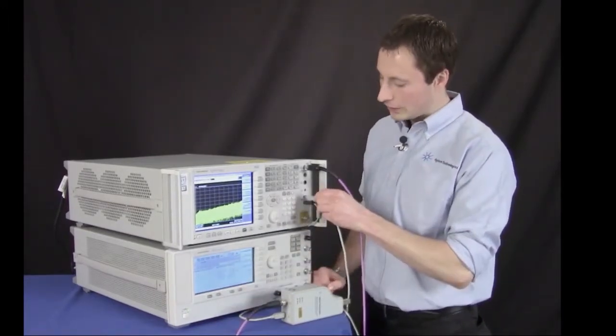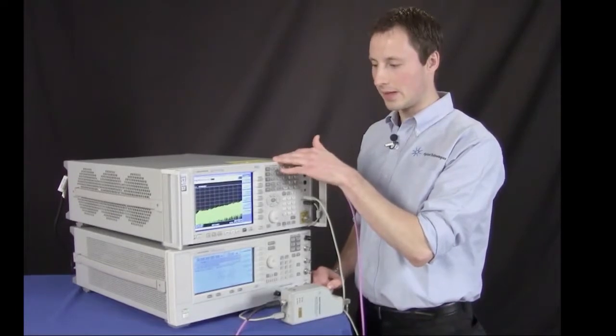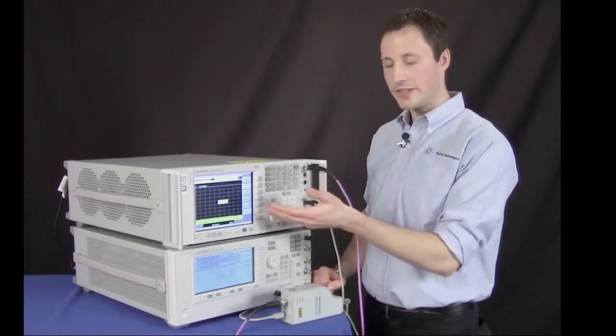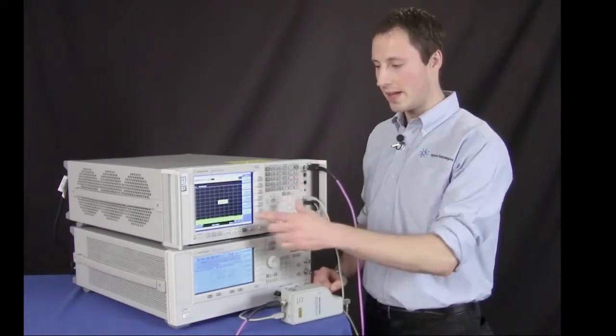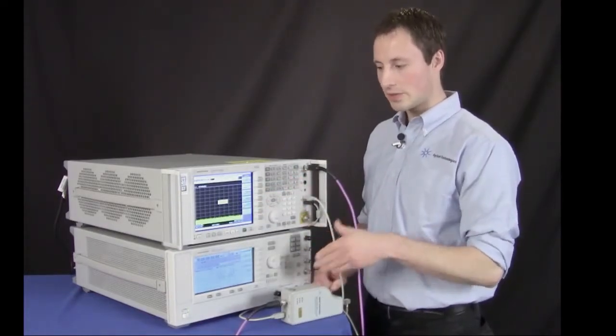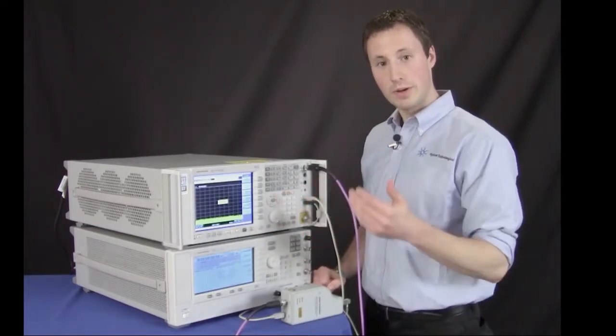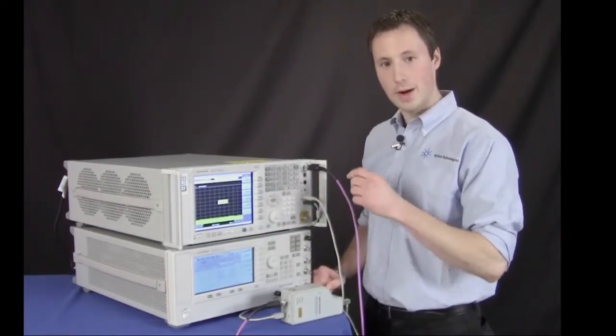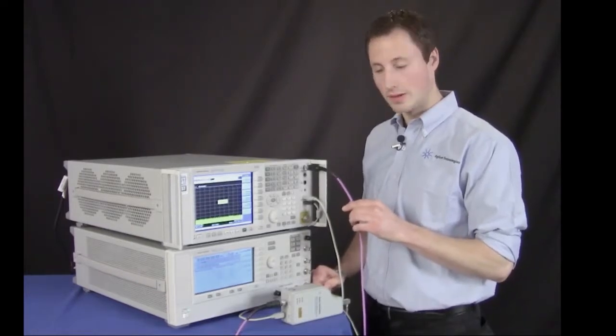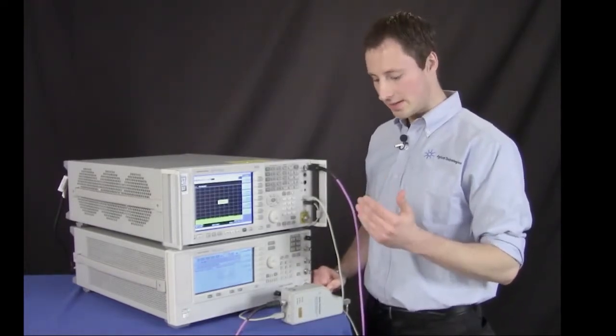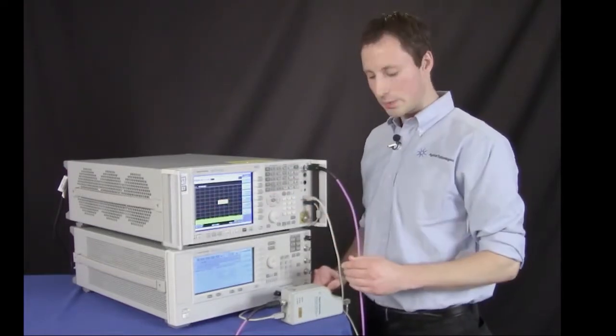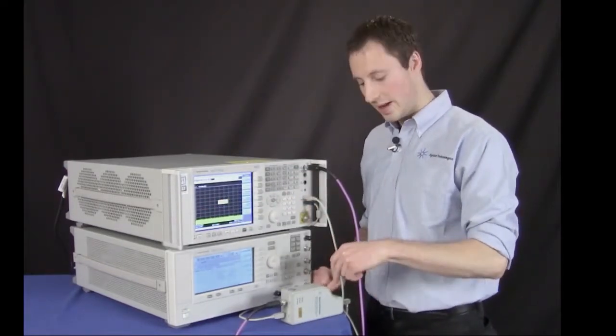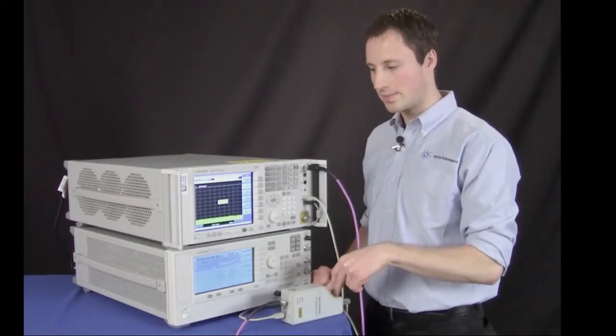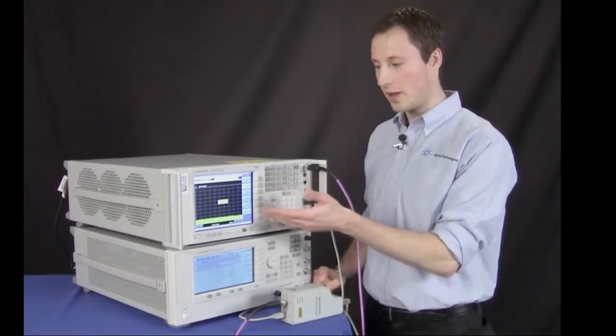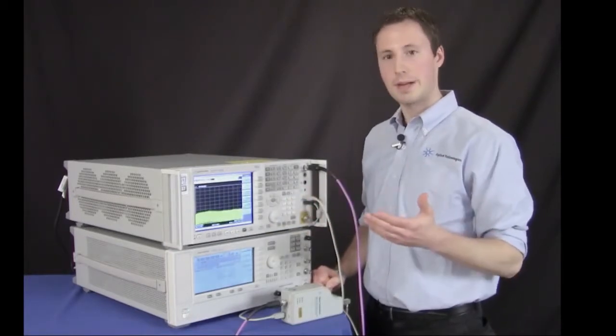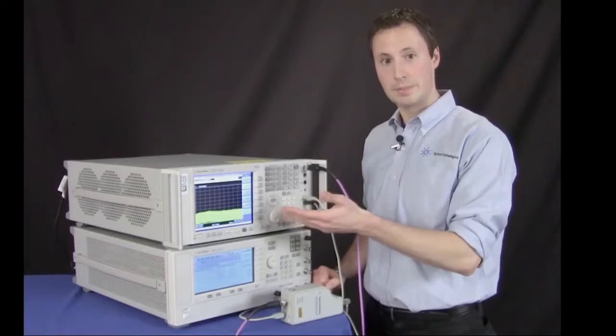Next, simply plug in the USB cable on the signal analyzer. Now, the signal analyzer will automatically detect the center frequency and the span of the mixer, and it will start aligning the LO. Now, what it is doing is it's compensating for any loss in this IF and LO cable and making sure that the power level is adjusted to be consistent across the entire frequency span relative to the entrance at the waveguide entrance. Now, when it is finished aligning, the mixer is all ready to make measurements, and that's how easy it is to set up and use.